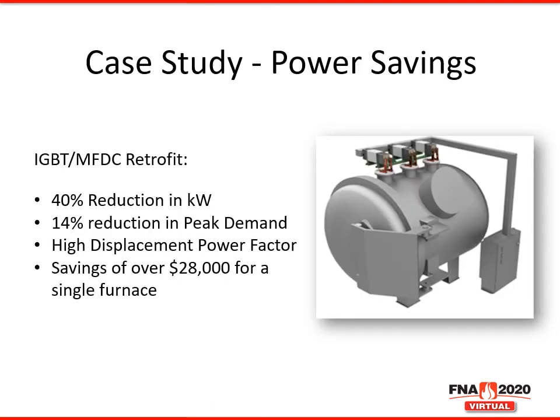In order to evaluate the IGBT MFDC power system, we're going to go over a case study in which we performed a retrofit of a vacuum furnace powered by a VRT. We directly compared the power characteristics of the two power supplies. From this case study, we will demonstrate a 40% reduction in kilowatt consumption, a 14% reduction in peak demand, and a high displacement power factor throughout the cycle. All of this results in lower cost for furnace operation.